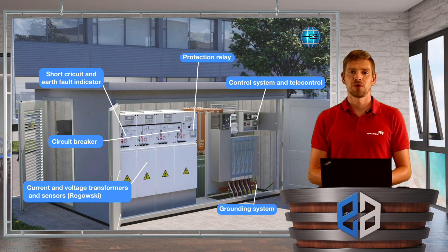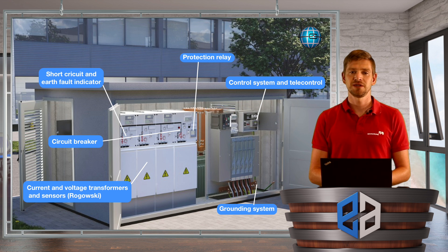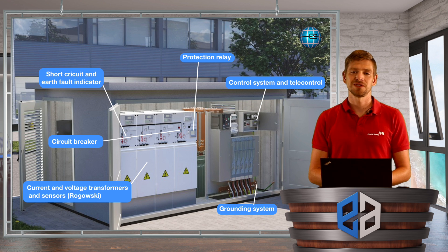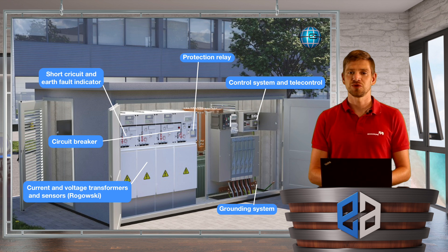In addition, we see more and more ring main units equipped with circuit breakers and protection relays, due to smaller space requirements compared to traditional fuses for medium voltage protection of the distribution transformer. We can achieve a much smaller footprint using gas insulated switchgear with these components. Of course, as with short circuit indicators, they need current and voltage sensors to bring medium voltage values to measurable values in the secondary world — these could be low power instrument transformers with very low burden or Rogowski sensors used for the protection relay or short circuit indicators.